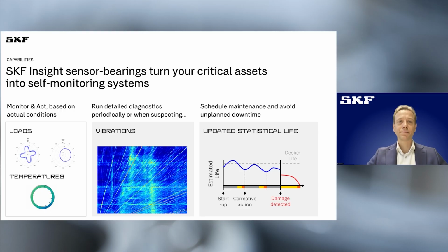Here we have SKF Insight sensor bearings turning a compressor or pump into a self-monitoring system. Starting from the left, we see loads and temperatures generated by a bearing in a screw compressor. In the blue polar plot, you see 4 lobes—the 4 lobes of a screw compressor. Every time a lobe passes the exit, there is a puff of air, and the bearing senses this puff 4 times per revolution, hence the graph with 4 lobes.